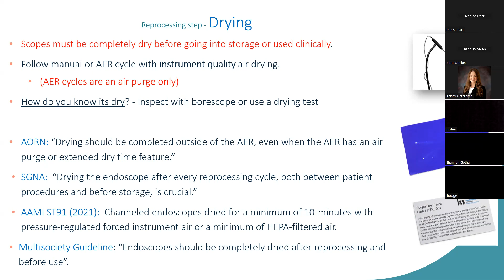On the flip side is a blue coloring. You would hold that at the distal end of a lumen device, including a flexible endoscope, while air is blown through the channel. Any residual moisture would splatter white. It would change the card to white. So this is something I recommend even infection preventionists consider doing when they make rounds. If you use clean technique, clean gloves, you don't have to reprocess the scope because you're just blowing air through the channel.